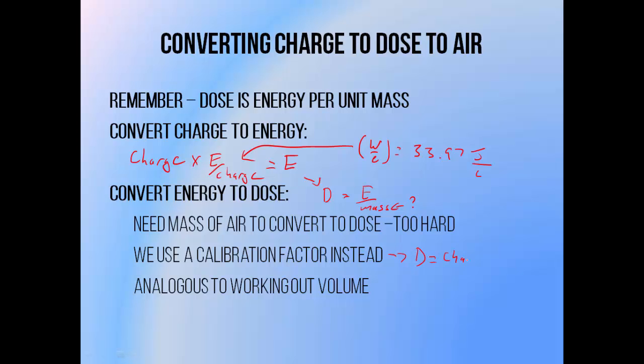This can be used to directly convert measured charge into dose to water. It's an approach that allows us to get around having to calculate the volume of the ion chamber.